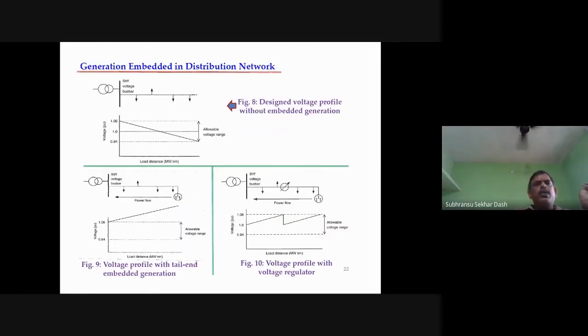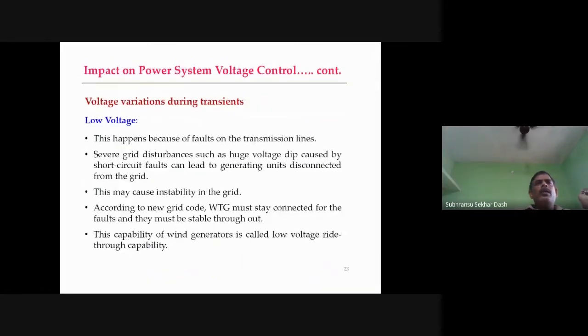Generation embedded in distribution networks, you can see the different diagrams. Low voltage variations during transients. This happens because of a fault on the transmission lines. A severe grid disturbance, such as a huge voltage dip caused by a short circuit fault, can lead to generating units being disconnected from the grid. This may cause instability in the grid. That is very important. See, the grid instability happens when there is a short circuit fault.